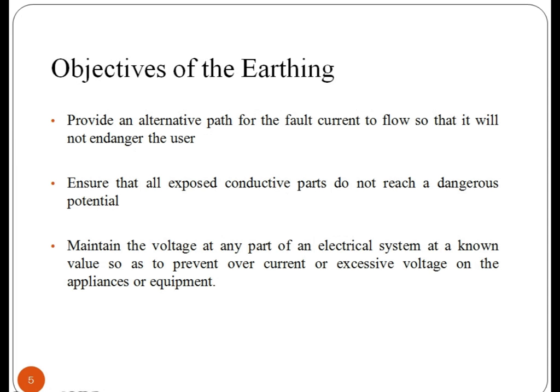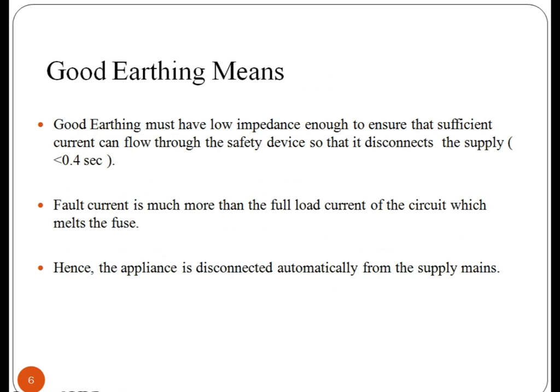What are the objectives of earthing? An earthing system or grounding system is a circuitry which connects part of the electrical circuit with the ground, thus defining the electric potential of the conductors relative to the earth's conductive surface. The choice of earthing system can affect the safety and electromagnetic compatibility of the power supply. Earthing affects the magnitude and distribution of short circuit current through the system and the effects it creates on equipment and people in the proximity of the circuit. It provides an alternative path for the fault current to flow so that it will not endanger the user and ensures that all exposed conductive parts do not reach a dangerous potential.